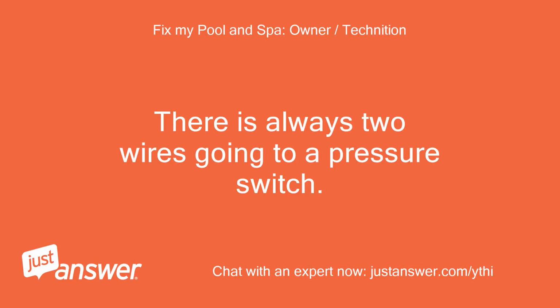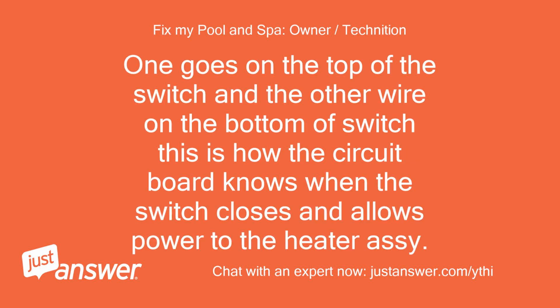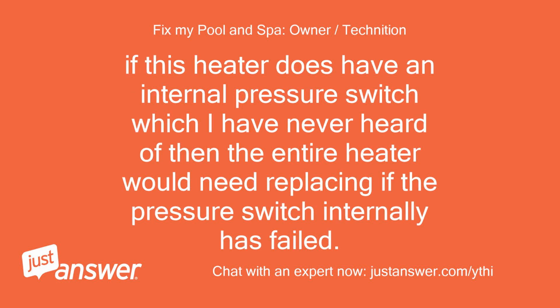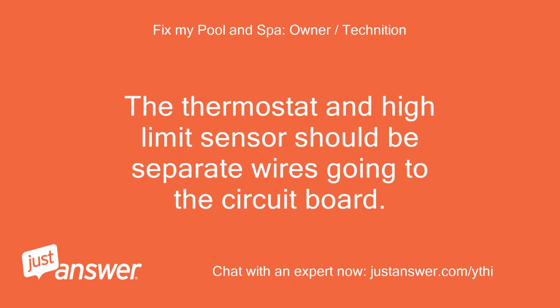There is always 2 wires going to a pressure switch. One goes on the top of the switch and the other wire on the bottom of the switch. This is how the circuit board knows when the switch closes and allows power to the heater assy. If this heater does have an internal pressure switch, which I have never heard of, then the entire heater would need replacing if the pressure switch internally has failed. The thermostat and high limit sensor should be separate wires going to the circuit board.